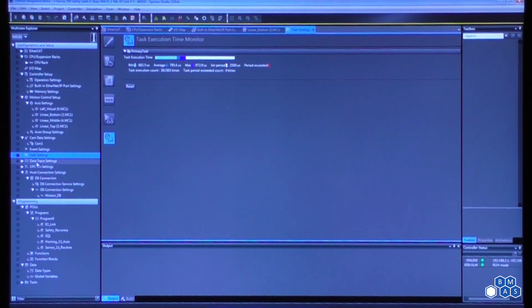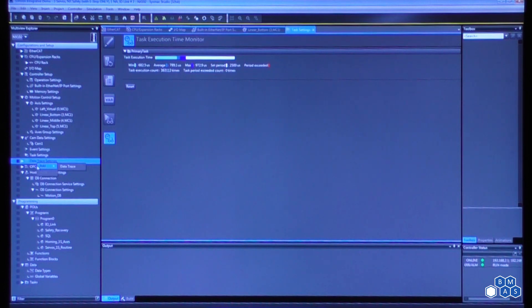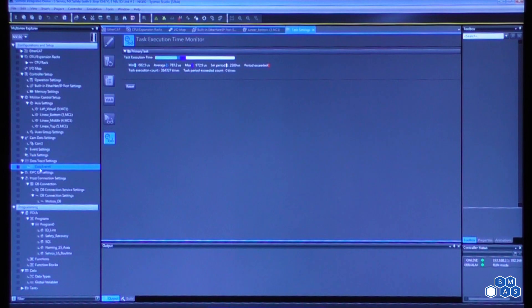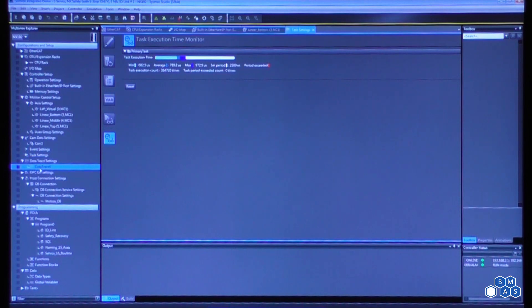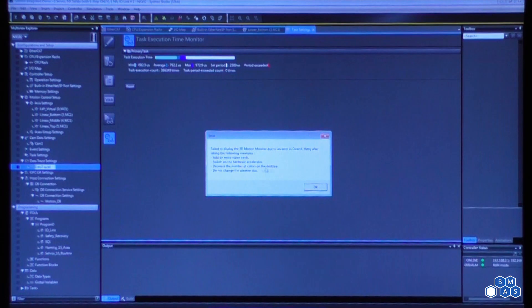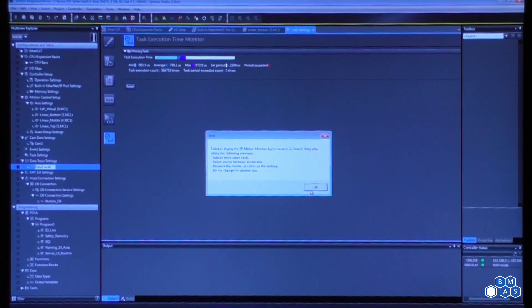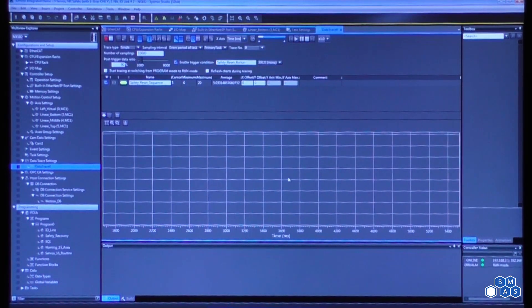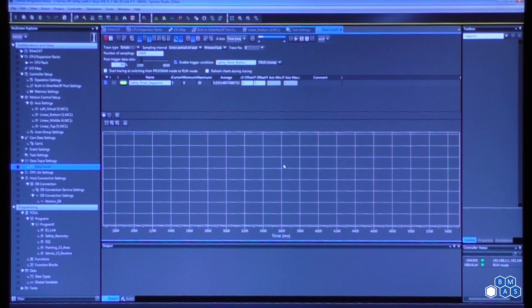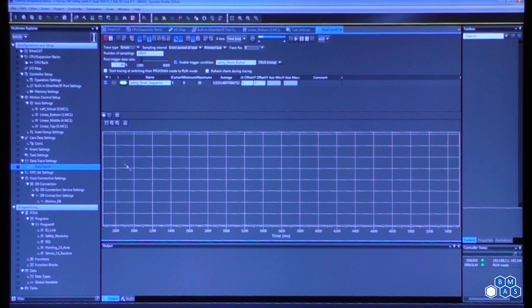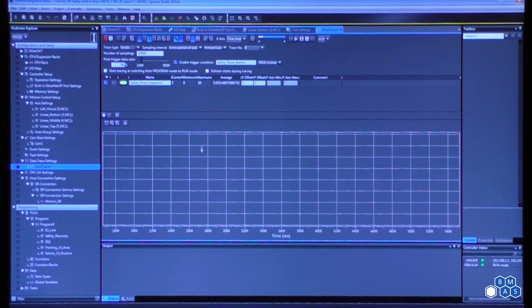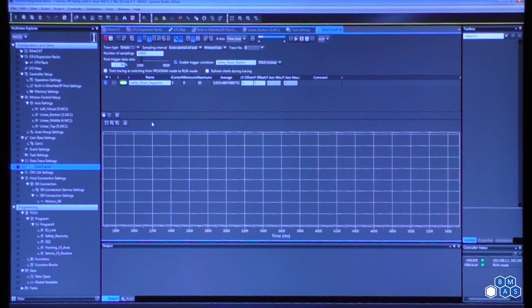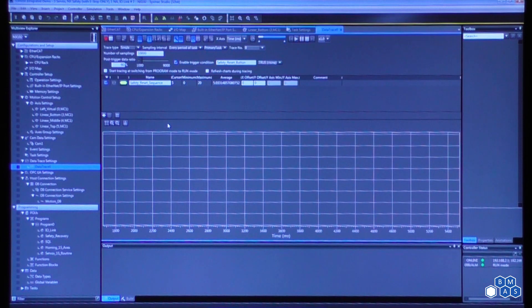The next thing is data trace settings. So this is if we're going to be doing any troubleshooting, you can create a data trace, and this data trace will open up a new window. You won't get that error because I'm running it in an Oracle VirtualBox that doesn't have a 3D graphics accelerator. So this gives us a means to—it's essentially like an oscilloscope. It gives us a means to look at a value over time, and we can capture that and then we can overlay so we can actually isolate problems that we might be experiencing, and then you can save those for viewing later.